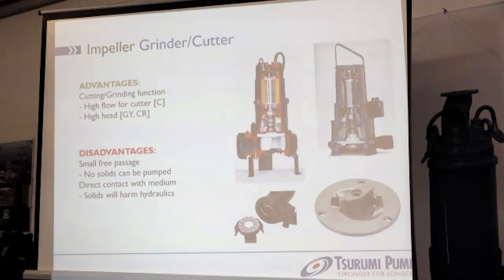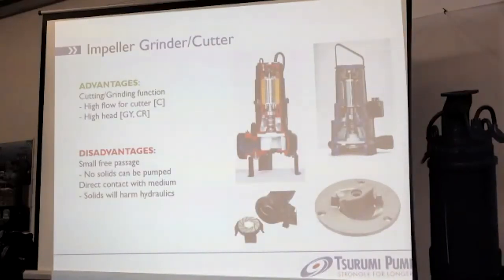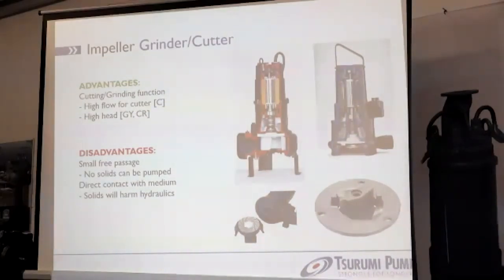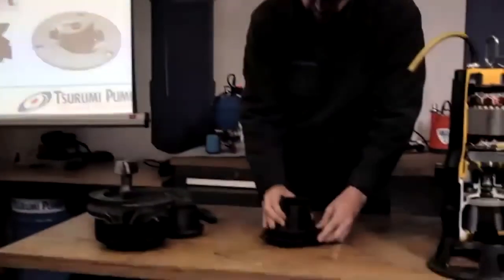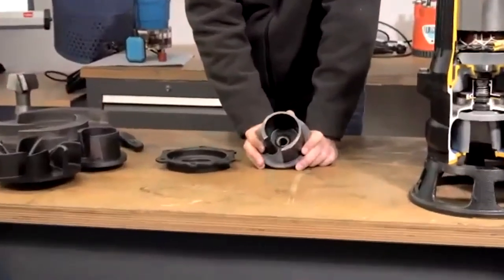Small free passage: we noted that. But solids cannot be pumped — if we have solid material like stones or sand, this will harm the cutting mechanism. If the medium has a high percentage of sand or bigger hard particles, don't go for a cutter unit. It would be better to use one of the impeller forms discussed before. Solids will harm either the cutting mechanism or the impeller itself.